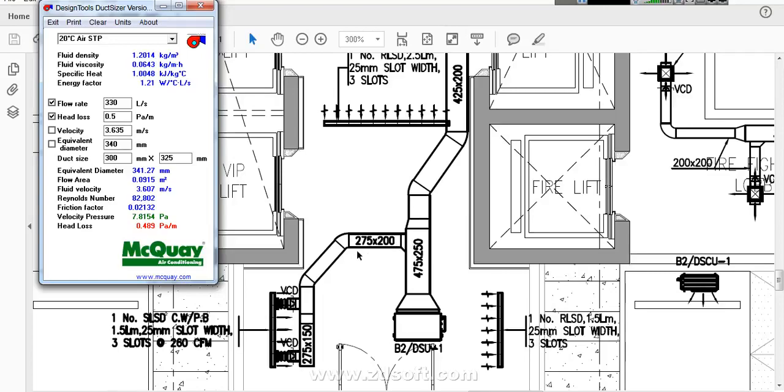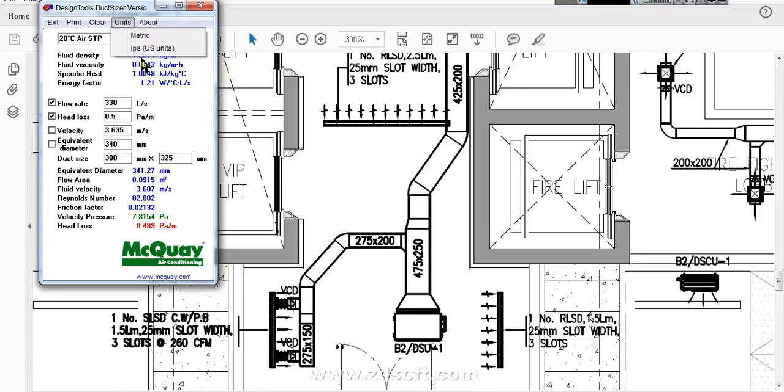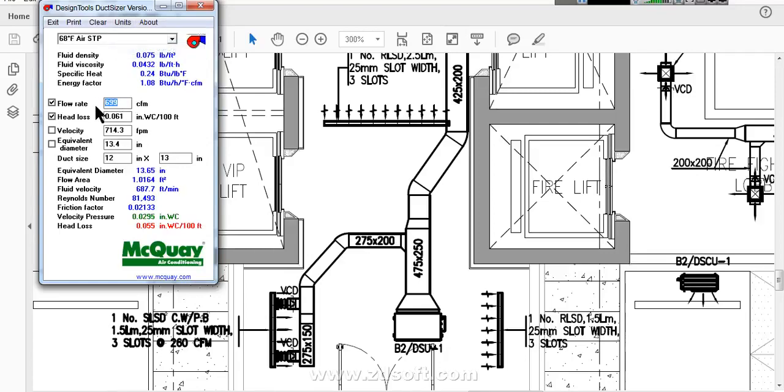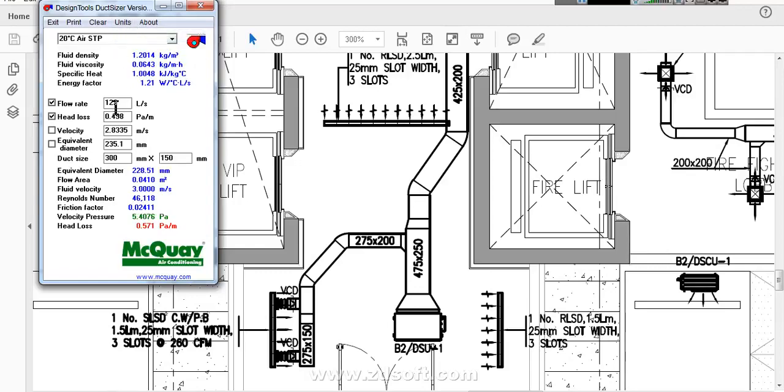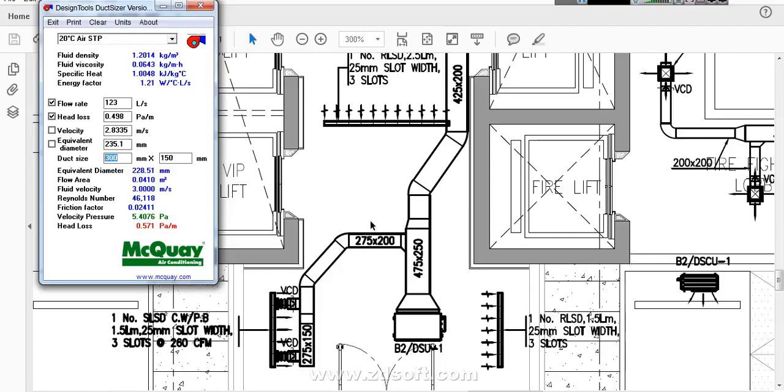Then here we taken a branch. This branch duct size what should be? For the branch, we have 260 CFM. So we will go to CFM, we will change here, and we will come back to this unit again. Because 260 CFM is equivalent to 123 liters per second. Here keep it as it is, no problem. This portion we will change the size. Here 275 is there. The first and second is 200. So we will enter duct like 275 by 200 is coming.